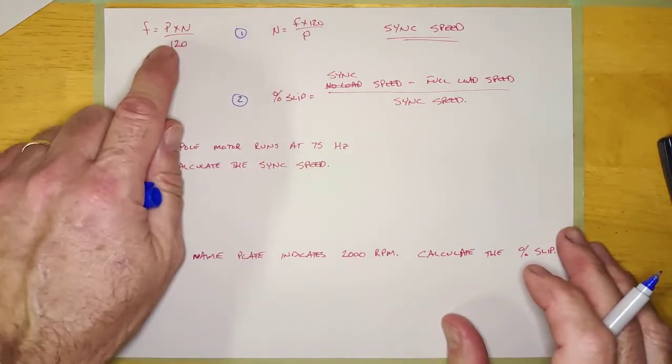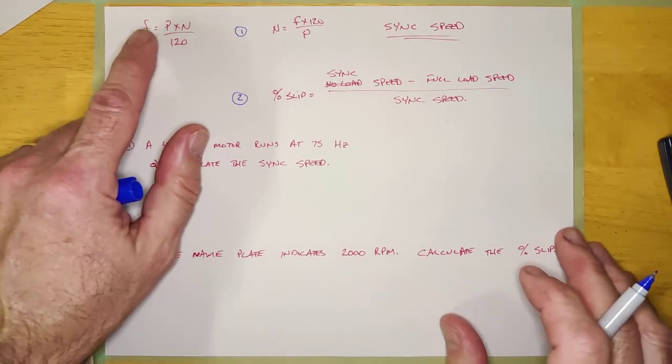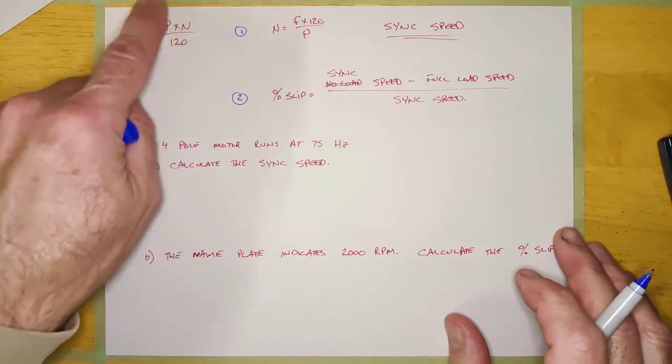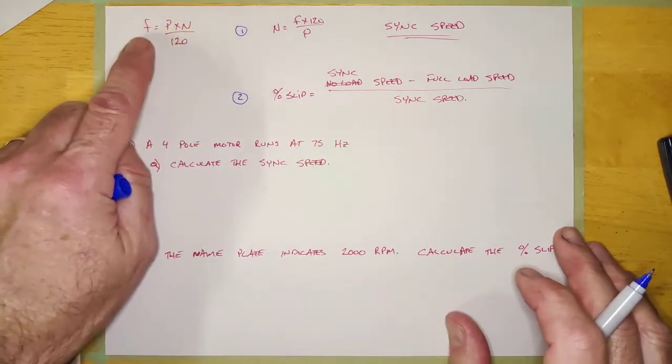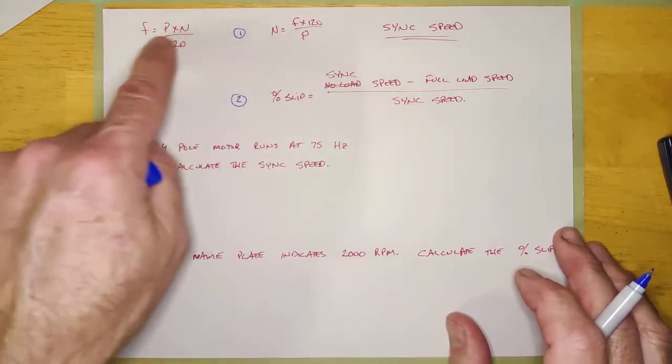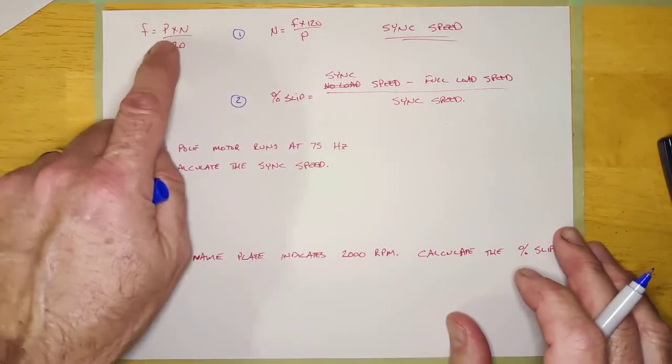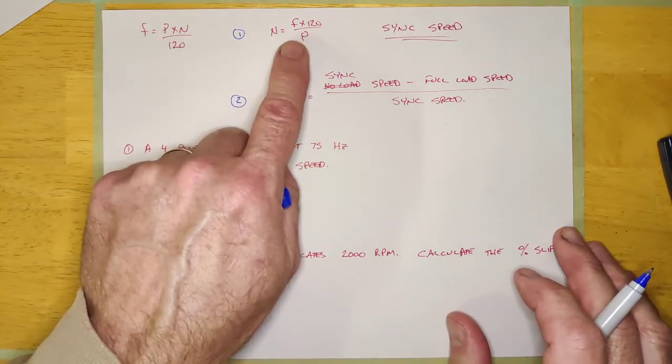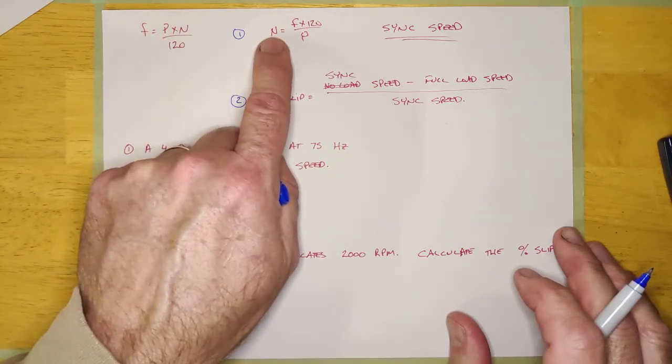And it comes from this formula right here, or at least this formula here is the same. This is f is equal to p times n over 120. This one usually is used to calculate what's the frequency output of an alternator if you know how many poles it has and how fast it's turning. So these two are the same formulas. This one usually refers to alternators. This one here refers to motors, and this one you're usually calculating speed.